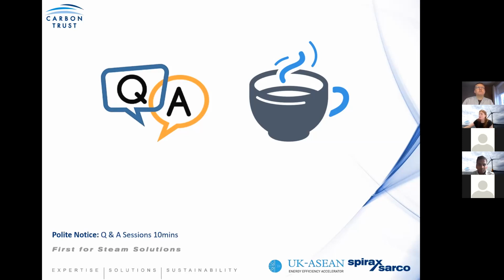Starting with some of the steam system fundamentals, the first question is, at which pressure can we ensure that the steam to end users is dry and saturated? There is no simple one pressure that fits all. If the steam boiler is designed to generate steam at 10 bar, then you should generate steam at 10 bar and, as recommended, reduce the pressure to a distribution pressure. Often what we're finding is that industry is being misled into reducing boiler pressure, say from a 10 bar design to 6 bar, because you need 6 bar at the end user, or distribution pressure.